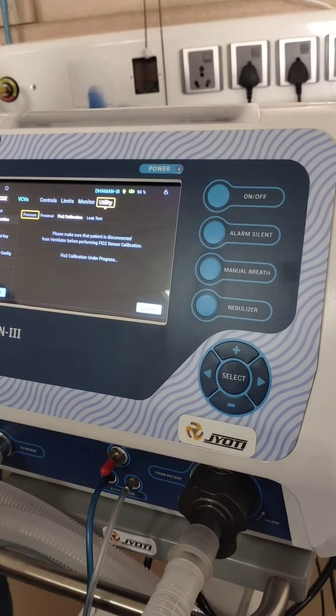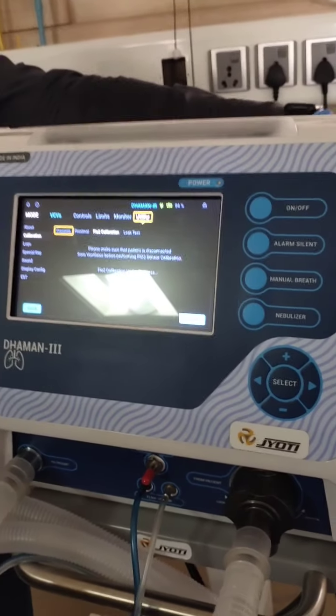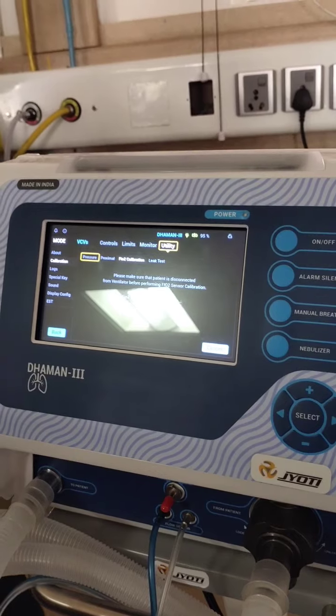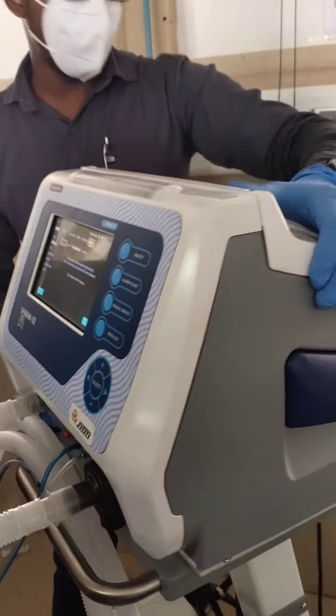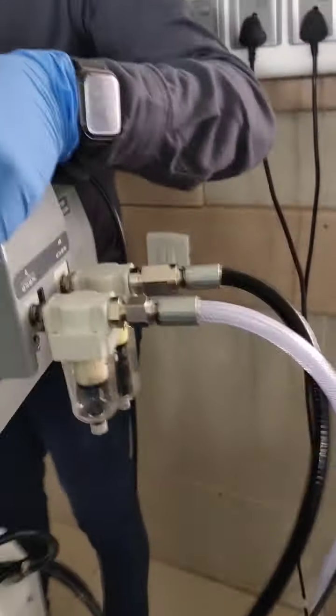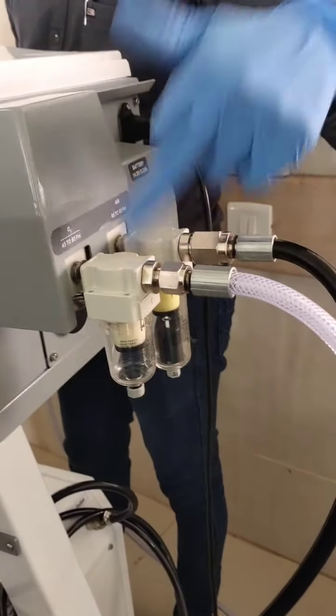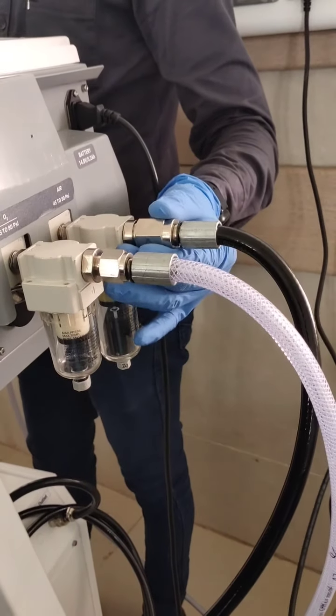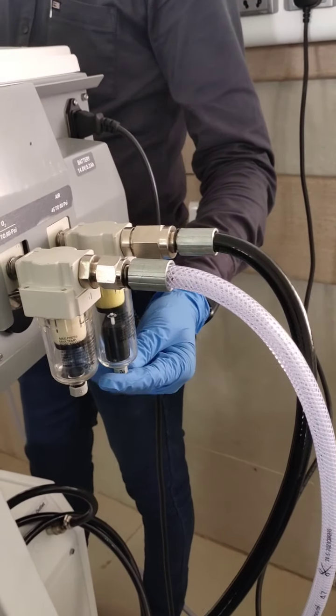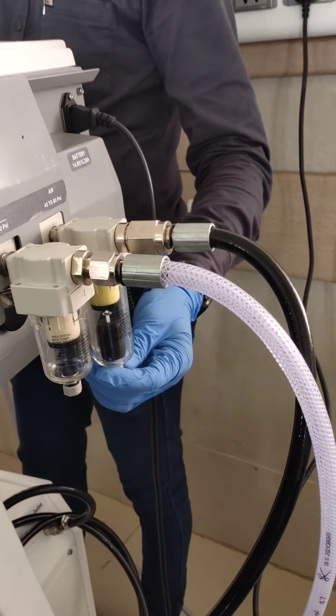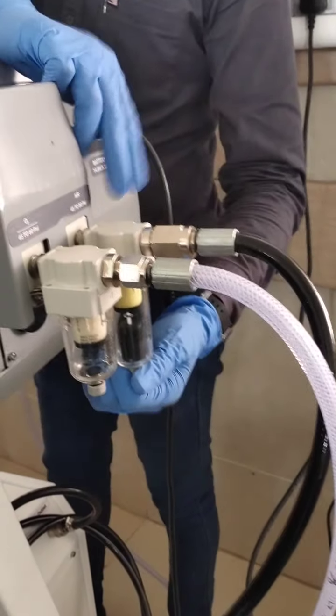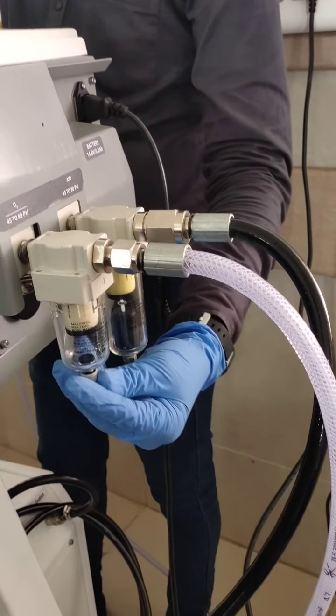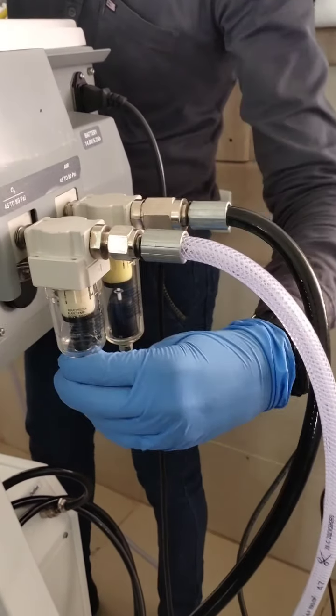Meanwhile, I will do the troubleshooting. What are the basic troubleshooting steps? We have an O2 and an air regulator on the backside. These two regulators control the pressure for the 3.5 to 4. If you are using the ventilator for a patient for more than 2 hours, you have to release it, because any air moisture or liquid will come. So you have to release it like this.